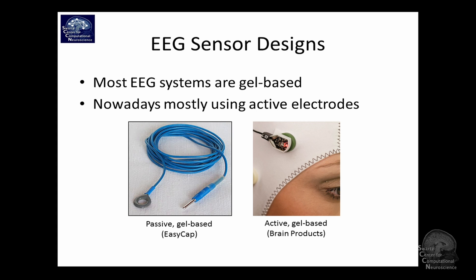There are also active electrodes which have little amplifiers in them. In that case, the signal is already amplified when it travels through the cable, as opposed to passive electrodes where you are transporting microvolts through the cable. So the electromagnetic artifacts are much lower in active electrodes, and also cable sway.